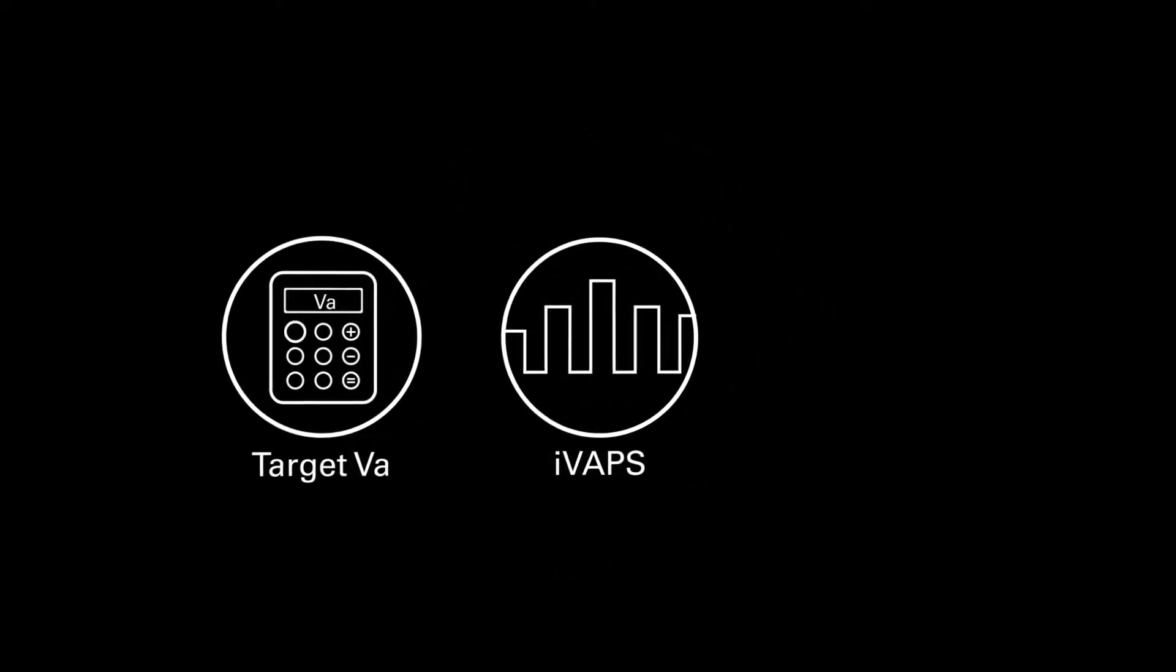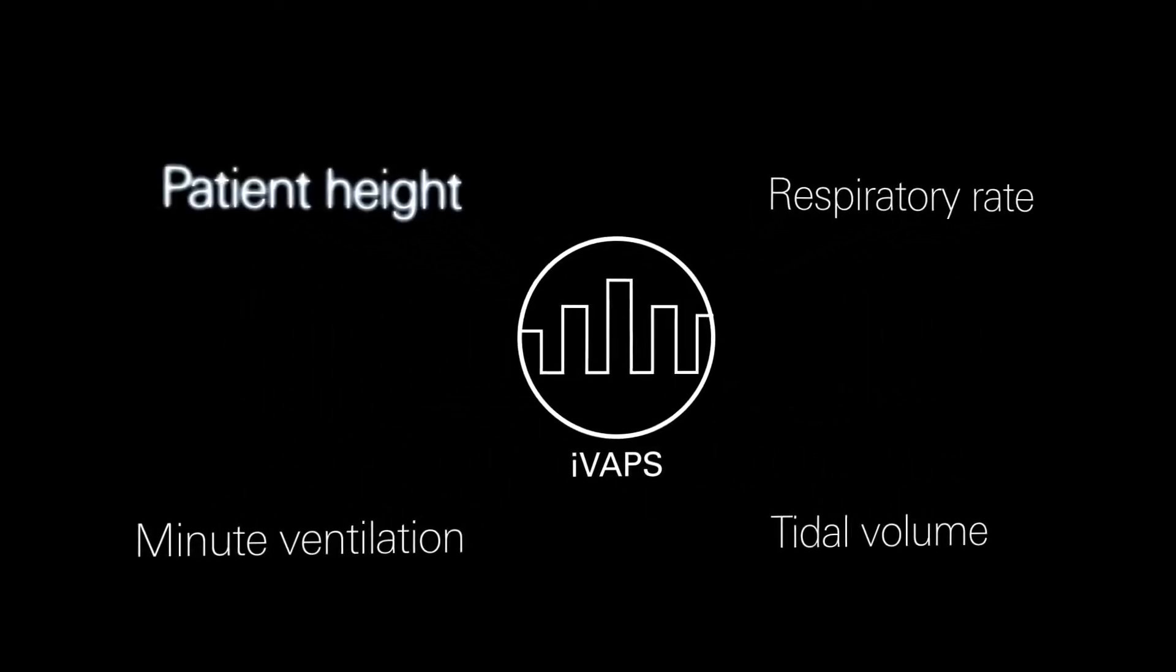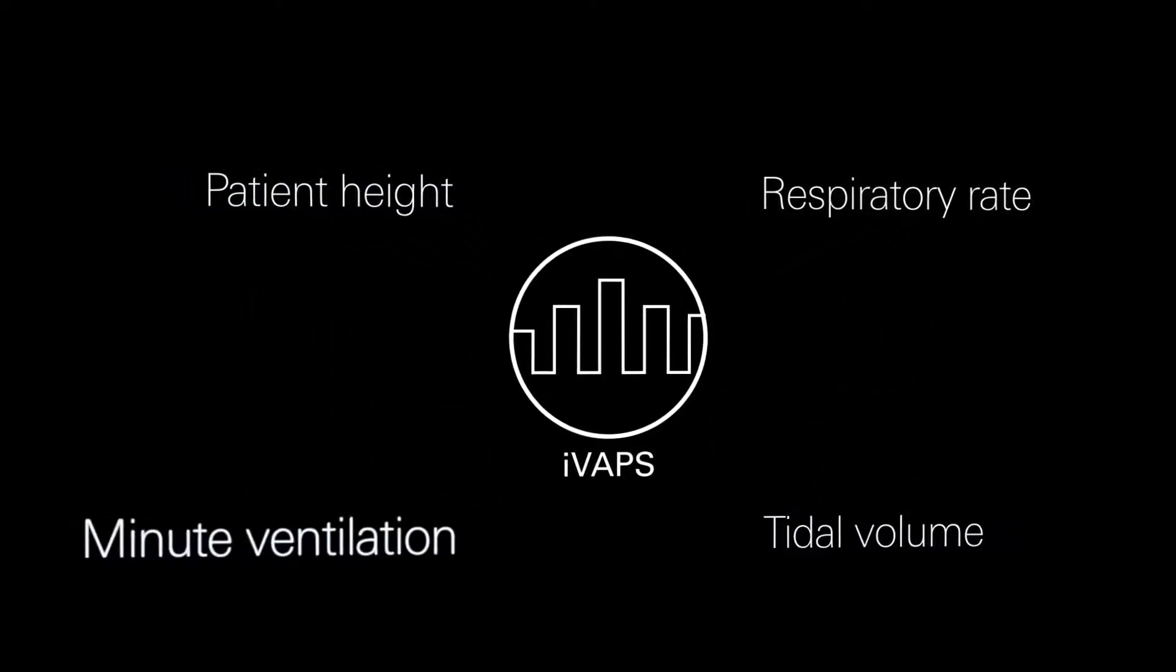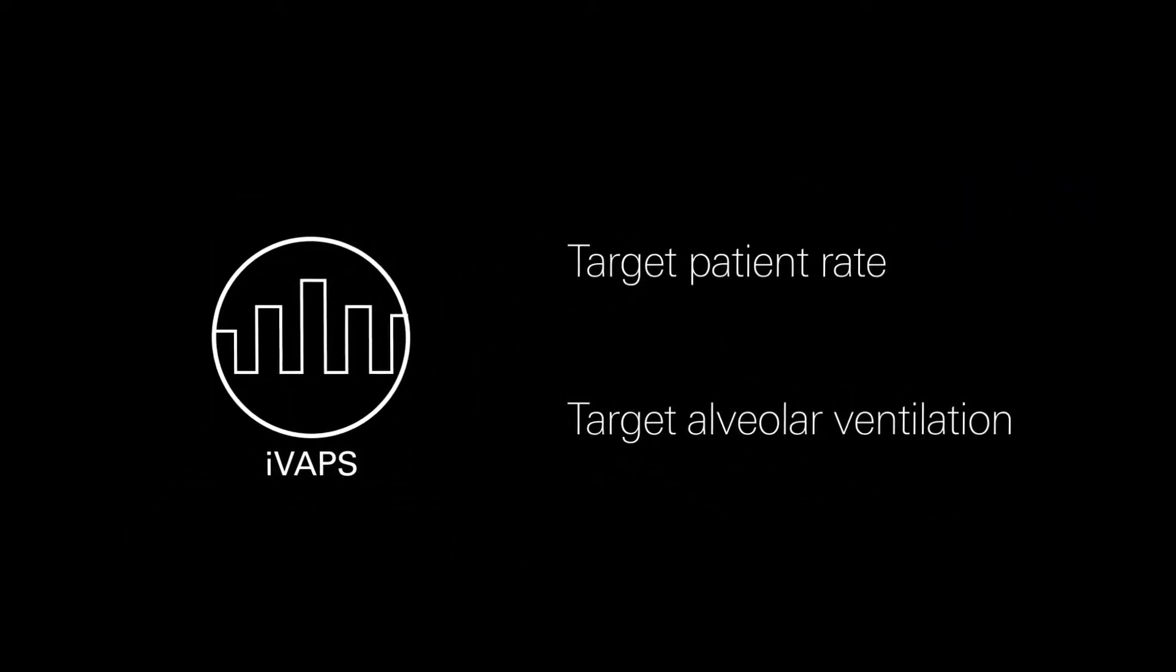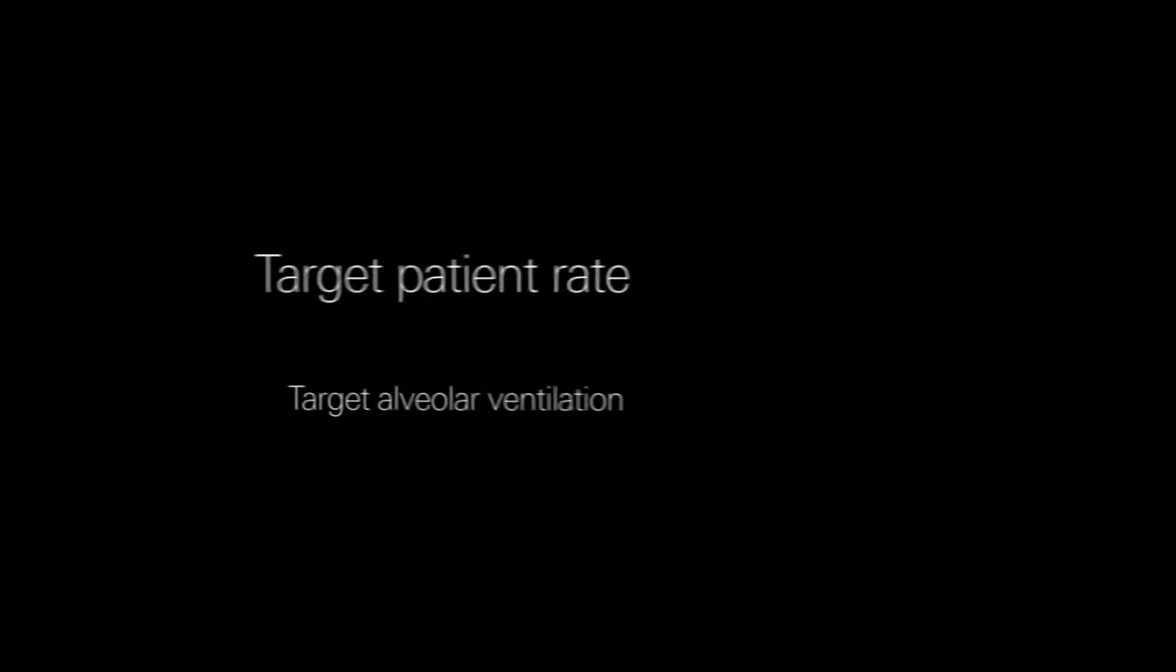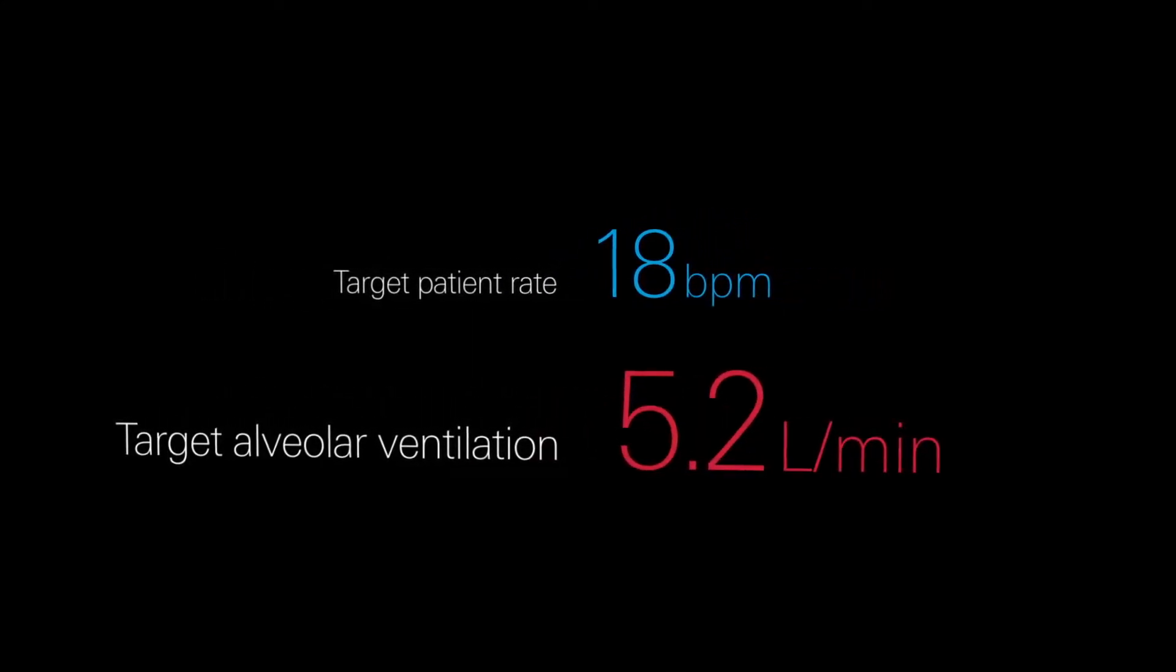And IVAPS is easy to set up, either manually or using the automatic Learn Targets feature. Using a range of clinical parameters that can be entered or learnt during setup, IVAPS sets optimal personalized targets for each patient, that is, target patient rate and target alveolar ventilation.